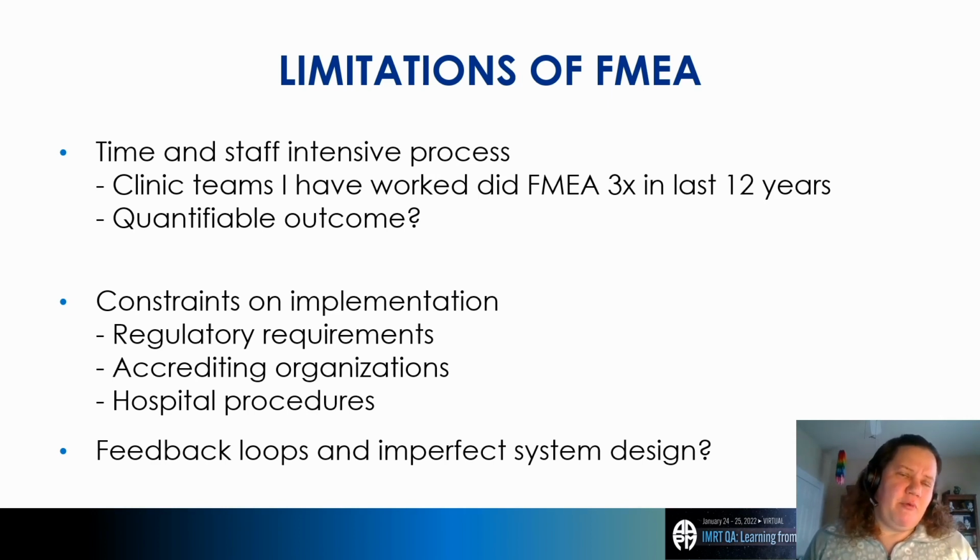The other obstacles we ran into were constraints on implementation. So there are regulatory requirements that we have to fulfill. Accrediting organizations have requirements, and there are also hospital procedures. And fun side note, we actually dropped a specific equipment test from monthly to quarterly in my institution, because our FMEA showed that this was a low risk thing to do and fairly high value in terms of time spent on that. And we get dinged at every accreditation for that, even though we show them the FMEA study. So there are still clearly some implementation things that have to be worked out.